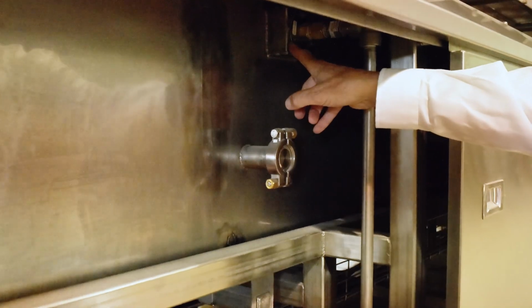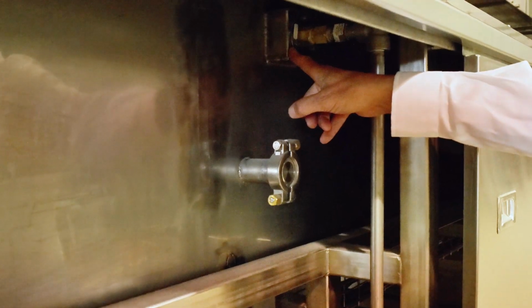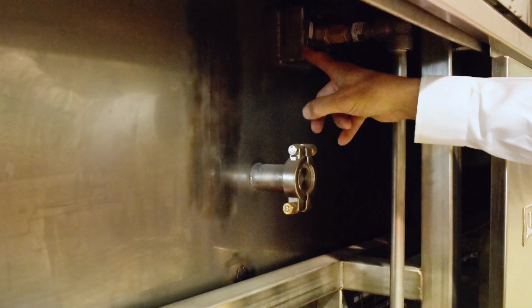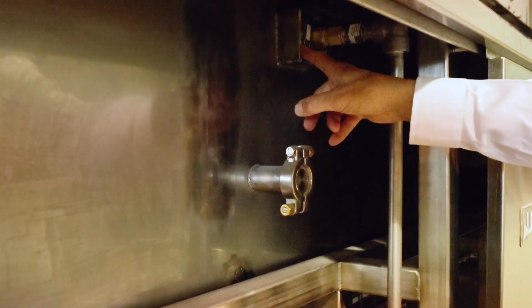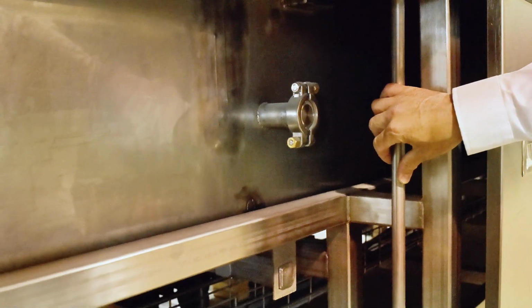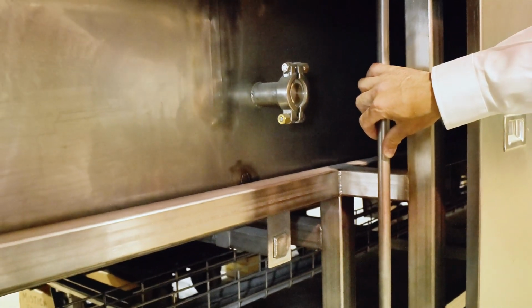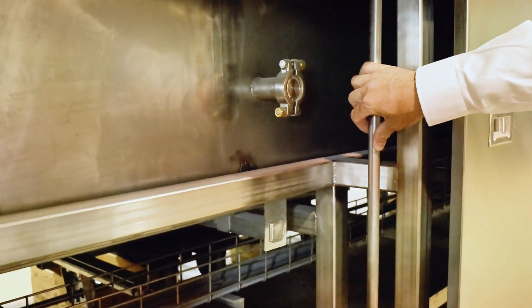This fryer has CO2 nozzles as standard equipment. So this is one of the two nozzles that introduce CO2 in the side of the fryer tank. All pre-piped, Schedule 80 piping according to code, and it's a standard feature on the Omar fryer.